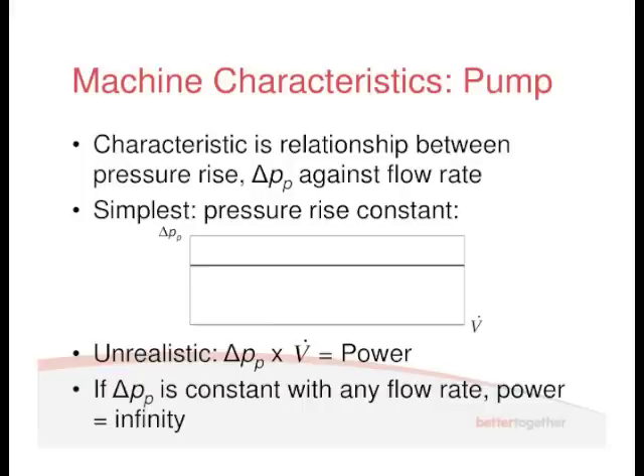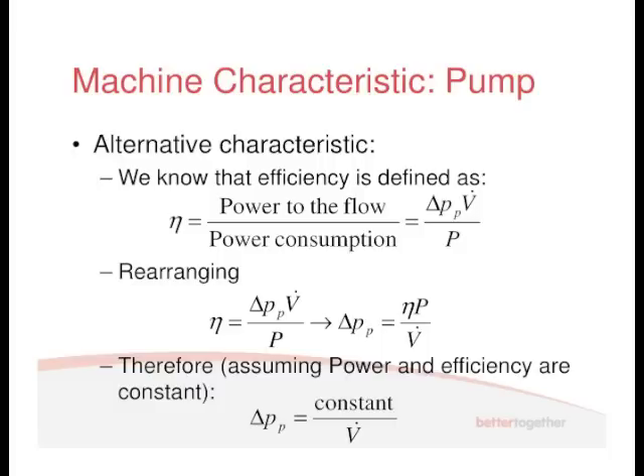Well, what's the alternative then? We know that efficiency, we talked about efficiency before, and we know that efficiency is the output power divided by the input power. So power to the flow divided by the power consumption. And we know that the power to the flow is delta P times V dot. So we can replace power to the flow with this, and I've replaced power consumption with big P.